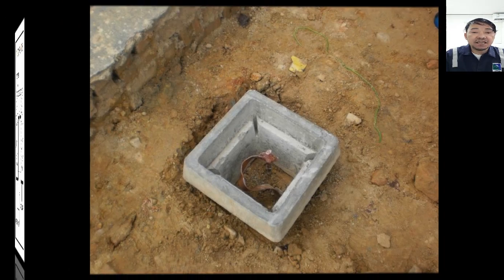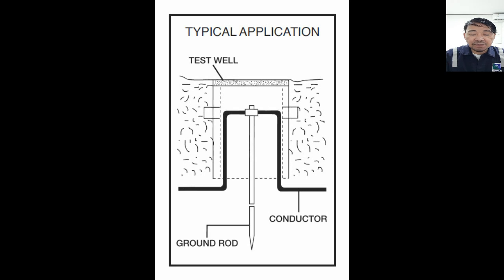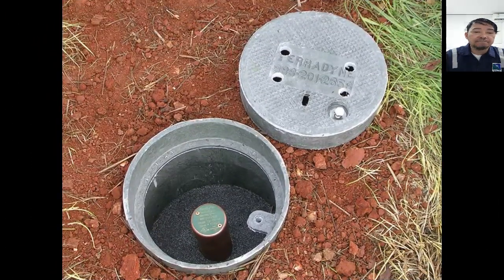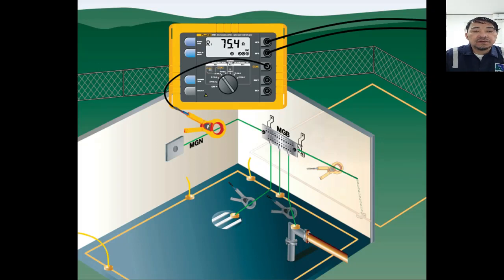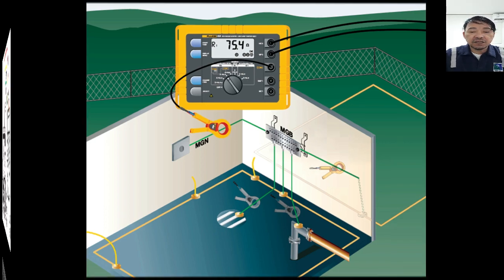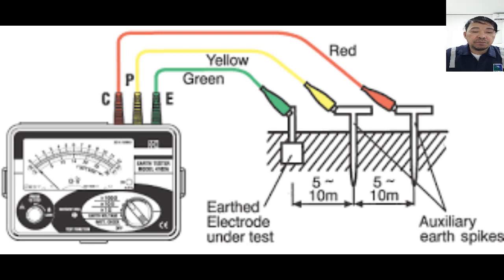New ground grid shall be provided with a test station or test wells to facilitate future tests. Test wells shall be reasonably distributed to cover the entire grid evenly. For the pre-commissioning test requirement, verify that resistance to remote earth of substation ground grids and or ground electrodes used for system grounding meets design requirements. Using a calibrated earth tester and with the use of a spike, a three-point method is used because of the reliability of the results. By moving each test spike from 5 meters and 10 meters in three different locations, the average value is calculated and it will be evaluated according to the requirements.